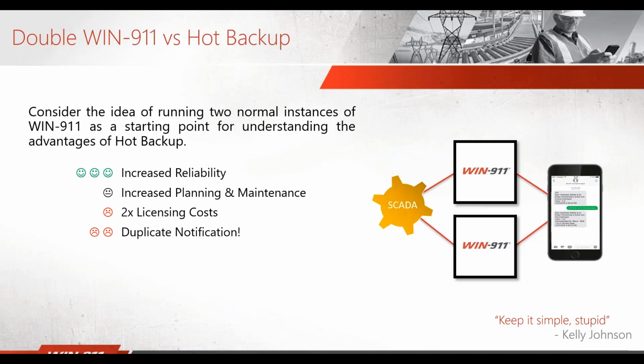There's a couple ways to do this. Well, you could have hot backup versus double Win911. Some customers will run 2 instances of Win911 looking at the same system. Some pros to that would be increased reliability. You've got 2 Win911s going. They're both getting alarms and sending alarms out at the same time, so you know there's at least 2 systems going. The problem here is the increased planning and maintenance. You're paying for 2 licenses instead of 1. And probably the worst one, duplicate notification. All your operators will get 2 alarm messages for every alarm that is sent out.